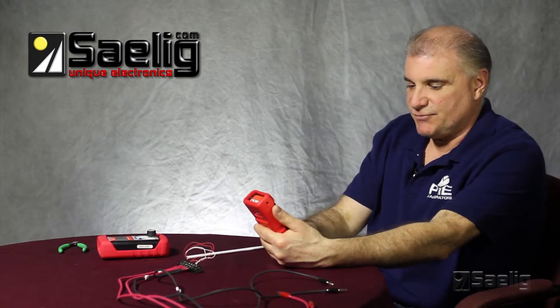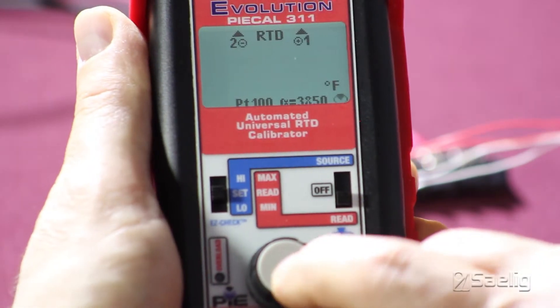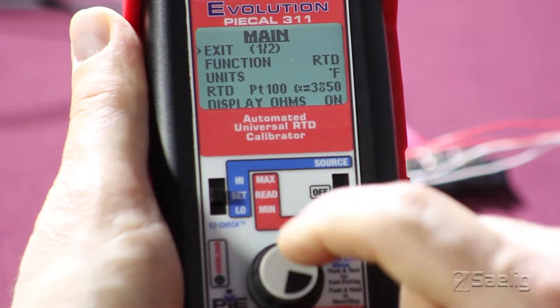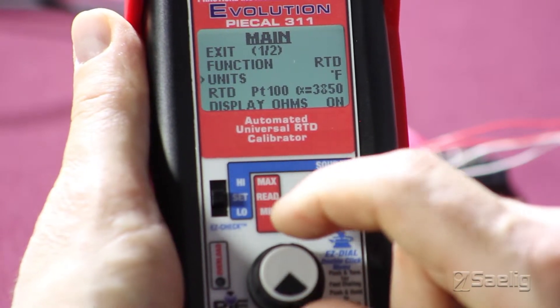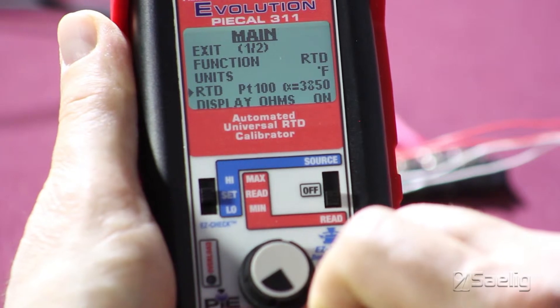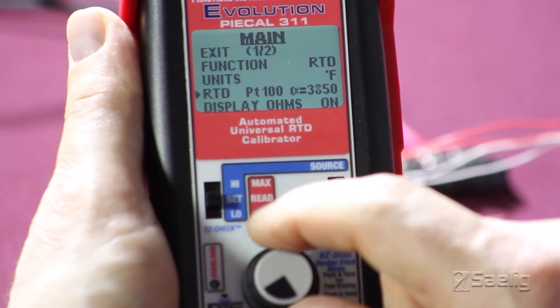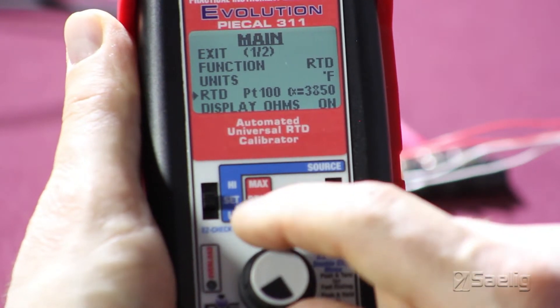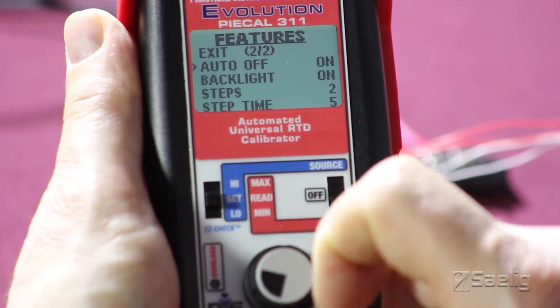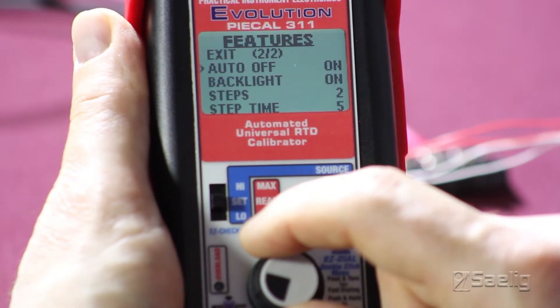We'll put the 311 into read mode and double click on the knob to get into the menus. We'll set this for degrees Fahrenheit. The RTD type is a Platinum 100 and the coefficient is 3850. The secondary display on the 311 will tell us what the resistance value is. We'll make sure that we have our auto-off set to on and our backlight set to on also.